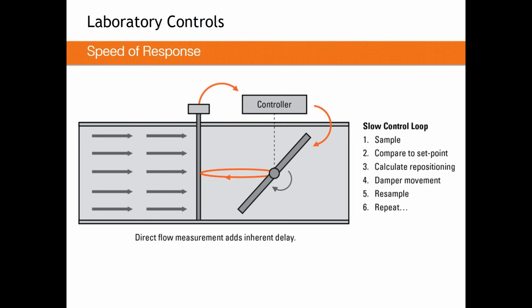What this number doesn't tell you is how long it takes them to complete the movement. If I need to go from 500 to 1,000 CFM, I don't really care how long it takes me to start going towards 1,000. I care how long it takes me to go from 500 to 1,000. That might be a couple of seconds. That's the number I need to know. But I might start to move that way in a fraction of a second. So one of these values, the total controlled response time, is a useful thing for us to know. The other is completely meaningless.